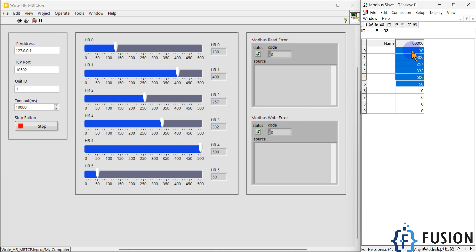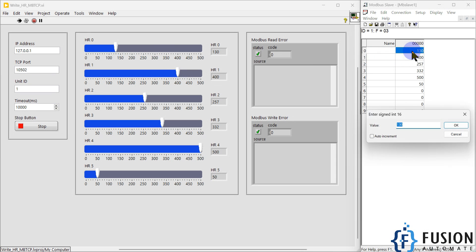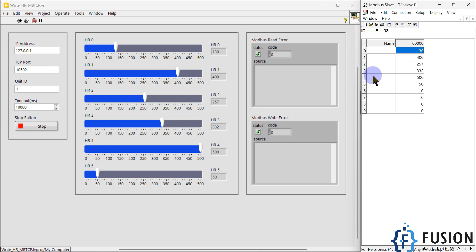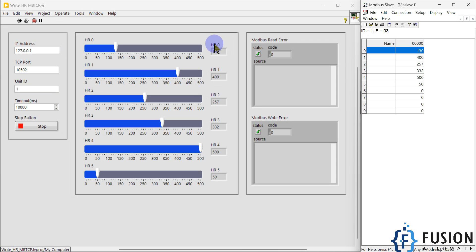This acts as a set point — we can control the set point from LabVIEW. If you write something from a different source, LabVIEW will overwrite it because LabVIEW continuously sends the set point value to the Modbus TCP device. If I write 96 here, LabVIEW will overwrite it immediately. You can also program it so that if the value is already correct, LabVIEW doesn't write again — only writing when the value changes.